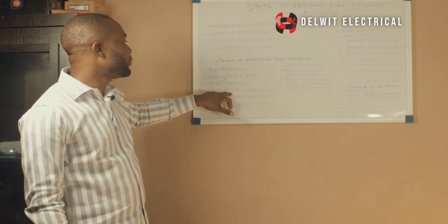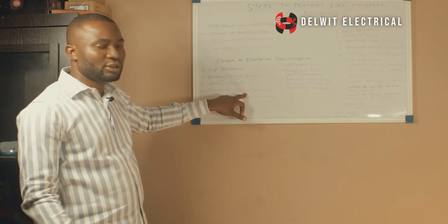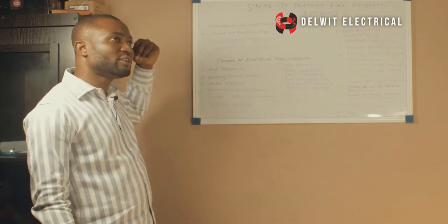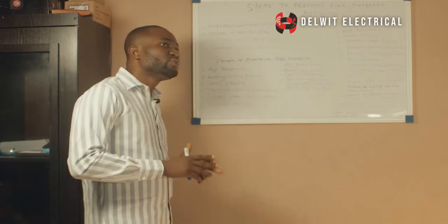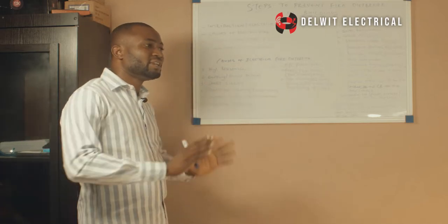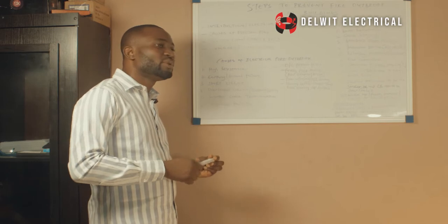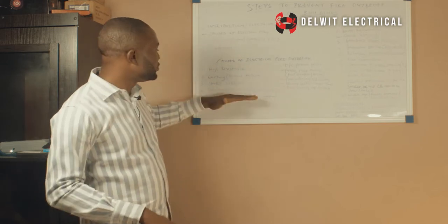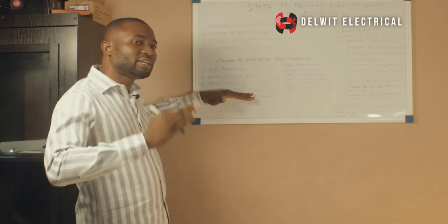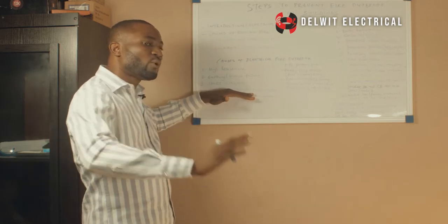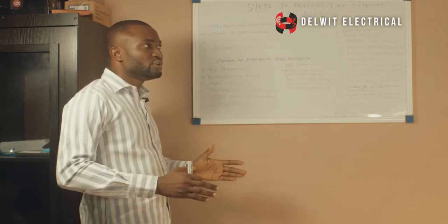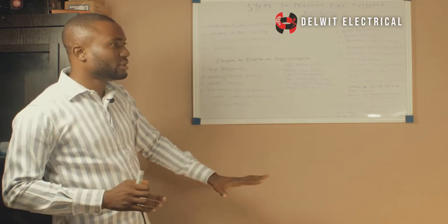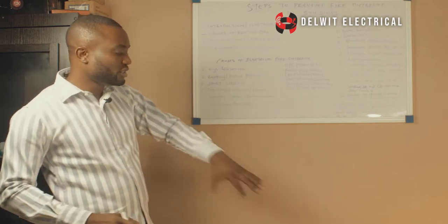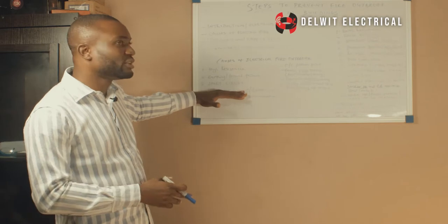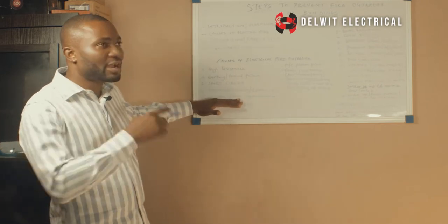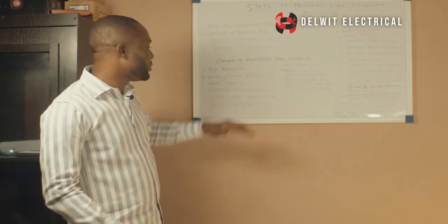Once you have overloaded that extension, you have overloaded the 13 amp socket and you have overloaded the circuit breaker. So it's advised, if it's for a commercial environment, that extension boxes should be eliminated. None of your staff should use extension boxes. When you are designing your office, make provision for 13 amp sockets within your workstation so that everybody knows, this is what I'm connecting. When you start using multiple sockets or extension boxes, it overloads the point and overloads the circuit breaker at the distribution board. Improper cable termination.